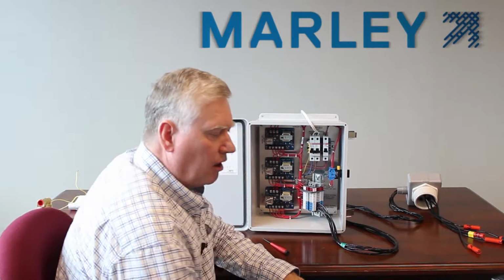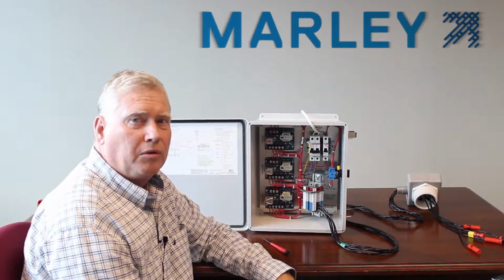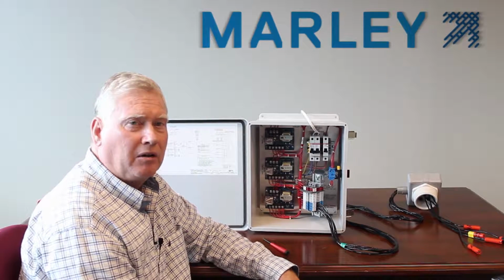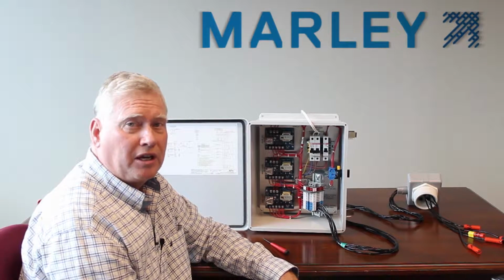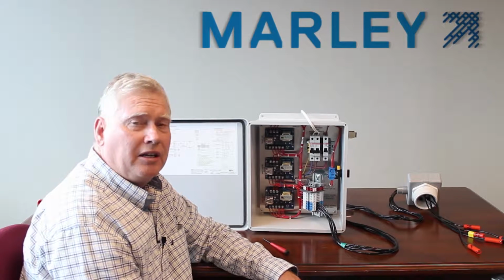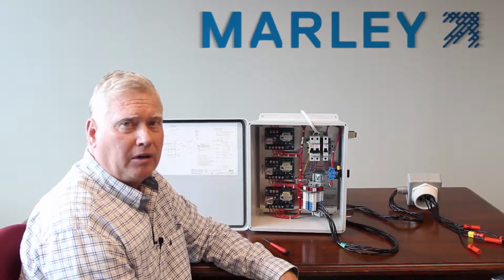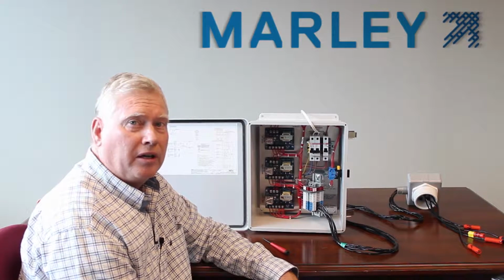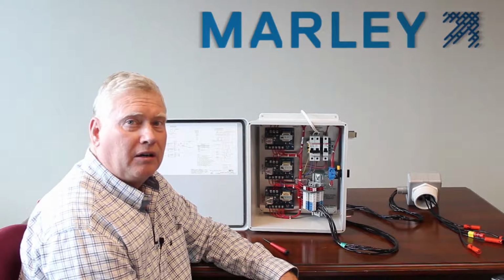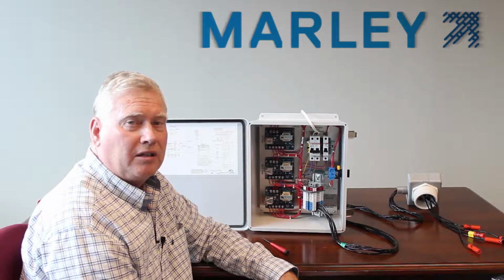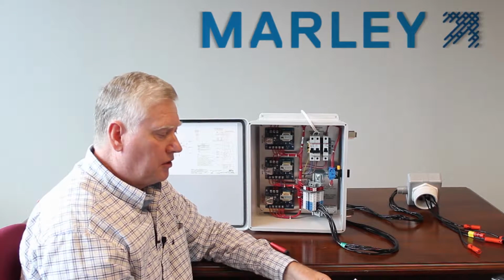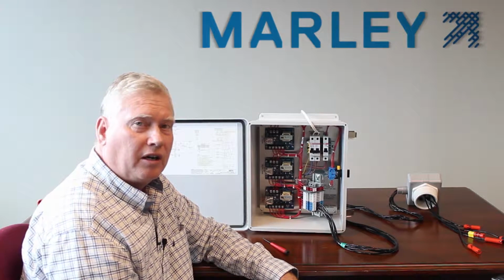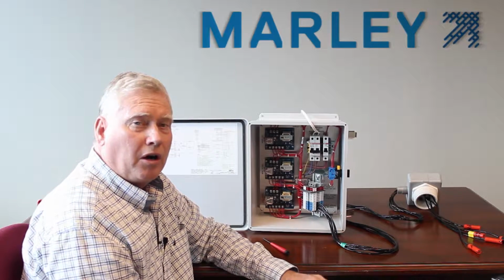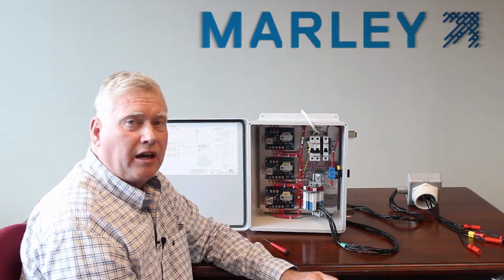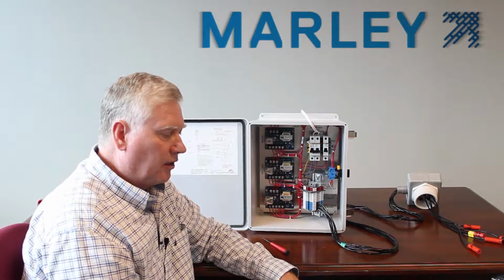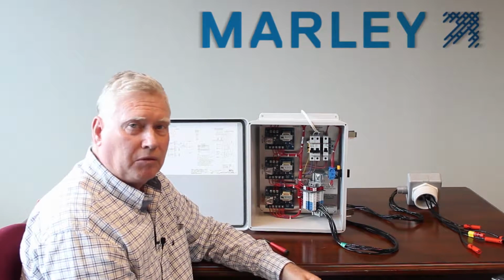So some of the issues are field wiring, usually associated with the electrical probes coming back to the panel. Maybe the customer added on to the probe sets to extend the length, and maybe they didn't terminate them properly under the correct wire number, or maybe they landed them under the terminal point and landed on the insulation. We'll talk about that later. Most of my calls are the field wiring type of errors. Some of the other issues in the field are that the probe heights are incorrectly adjusted inside the tower. And if you watch parts 1 and 2 of the video, you'll see how to make those adjustments. The other call we get back is that the solenoid does not operate. We'll talk about that a little bit later.